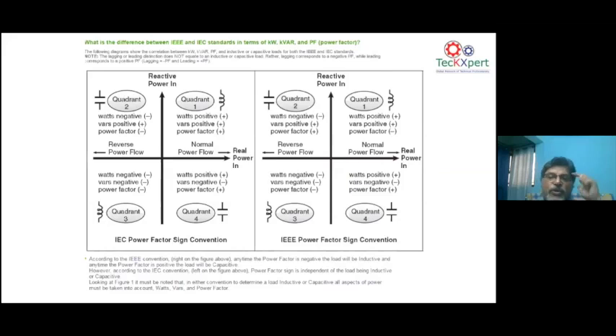There's something called 4-quadrant operation. Now, it is quite possible in a solar application. Sometimes the solar plant is generating power and exporting to the grid, and at some other time the plant is consuming power from the grid and the solar plant is not generating. Or there's a combination of the two.